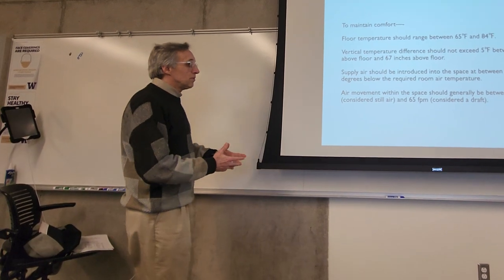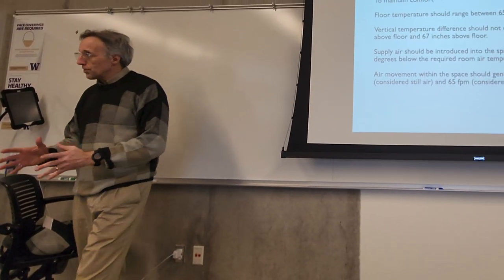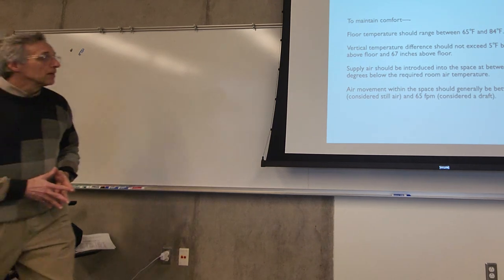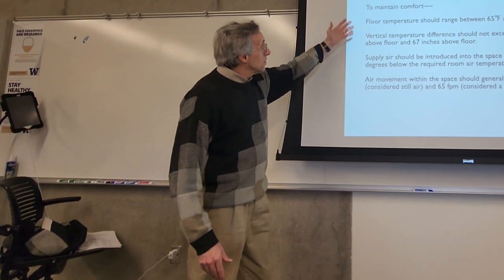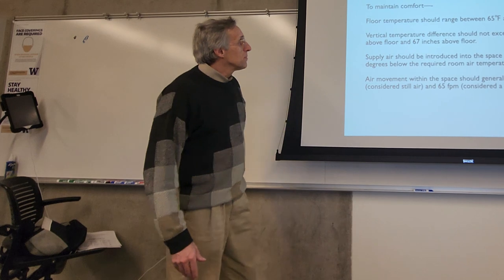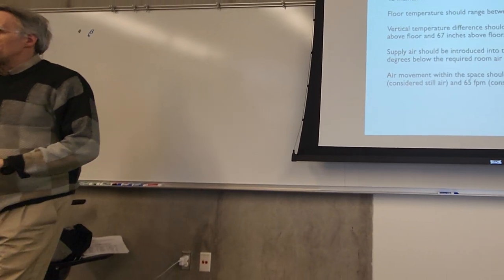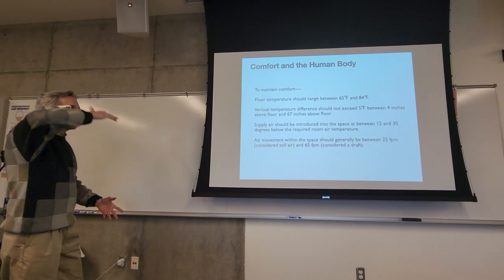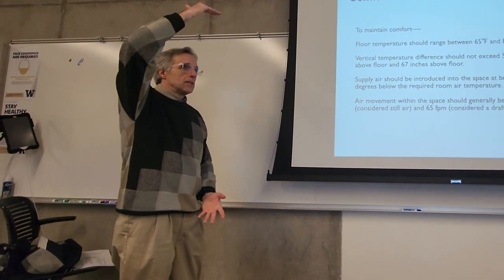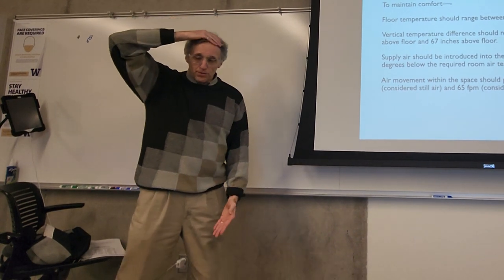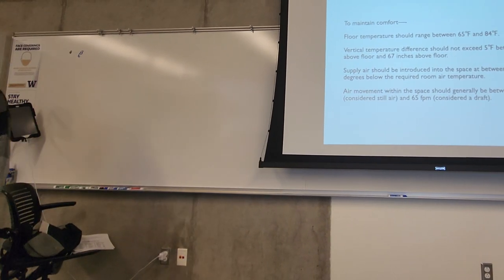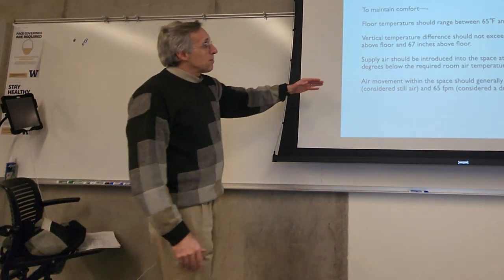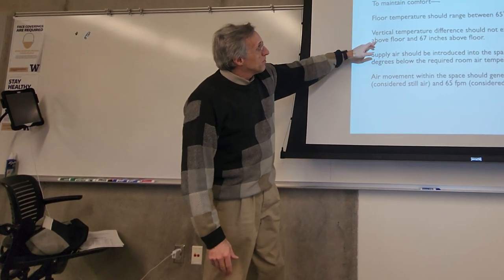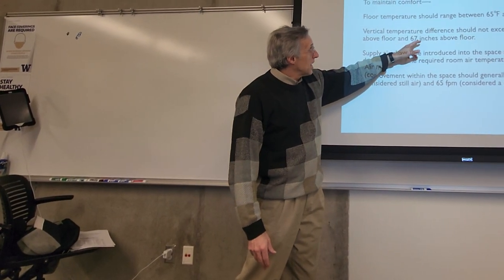So this helps you to really target your design to culture, people, how they're dressing, what they're doing in daily life. So, some rules of thumb for floor temperature: our bodies are very sensitive to vertical variation in temperature. We're not so sensitive if it's colder going up. We don't really notice if our head is colder than our feet, but we really, really notice if our head is warmer than our feet. And the rule of thumb is not more than 5 degrees between 4 inches above the floor and about five and a half feet above the floor.